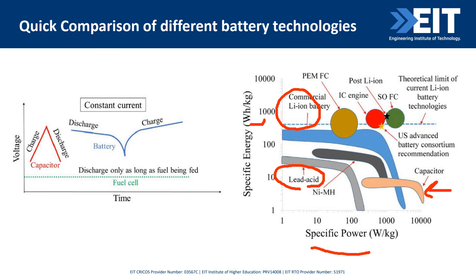Another thing we need to consider is the type of load that I have. Sometimes I have a load that requires a high amount of power but for a short time. That means I need to select a battery that can discharge fast, because one of the important factors in these batteries is their discharge rate. Sometimes I can discharge the battery at its nominal power or nominal energy rating; some batteries I can discharge at, let's say, half of that, and so on. So this is another important factor that I should consider.